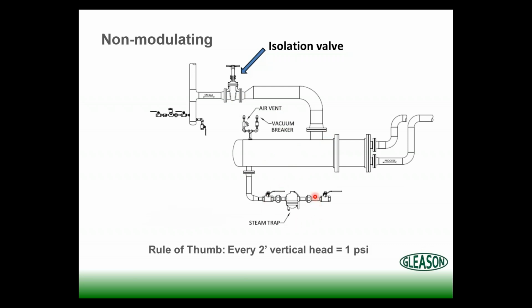Point is, we have to be very aware that if we have an elevated condensate return line above this heat exchanger, then we need to remember that for every 2 feet of vertical head, that's about 1 psi of back pressure, as the rule of thumb in the steam world. We can accomplish that because we know our steam pressure is not going to change. We just have to make sure we have enough differential across that steam trap, so when it opens up, we have enough pressure to evacuate the condensate.